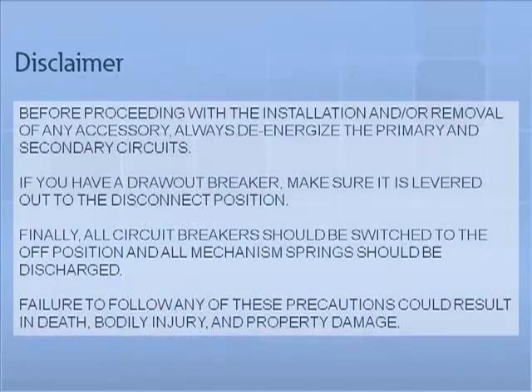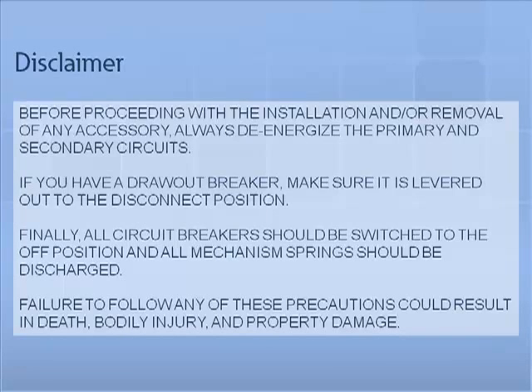Before proceeding with the installation and or removal of any accessory, always de-energize the primary and secondary circuits. If you have a drawout breaker, make sure it is levered out to the disconnect position. Finally, all circuit breakers should be switched to the off position and all mechanism springs should be discharged. Failure to follow any of these precautions could result in death, bodily injury, and property damage.